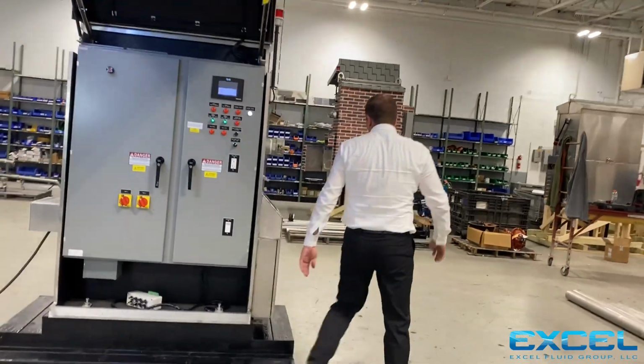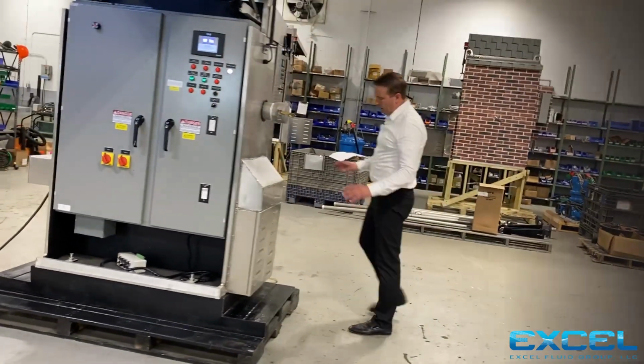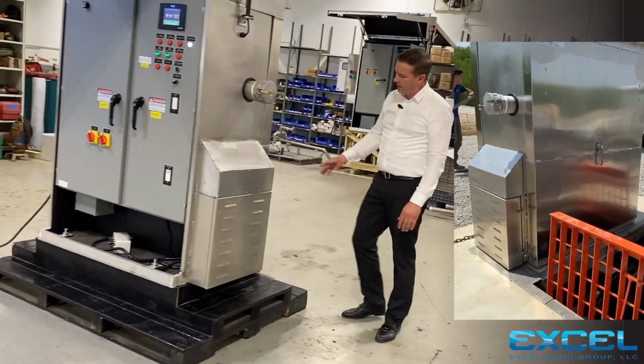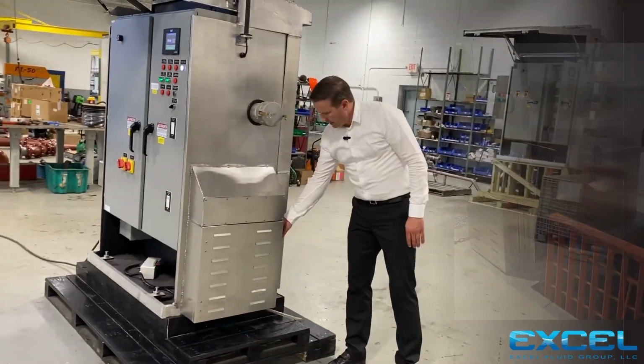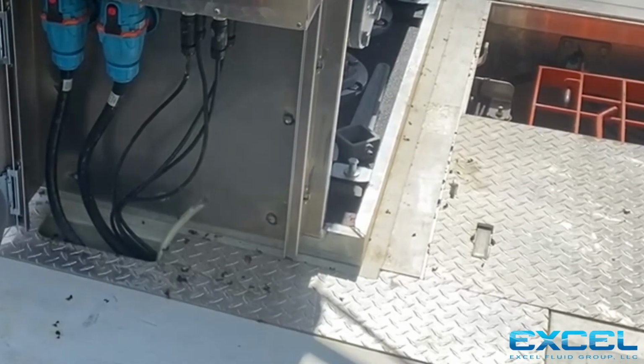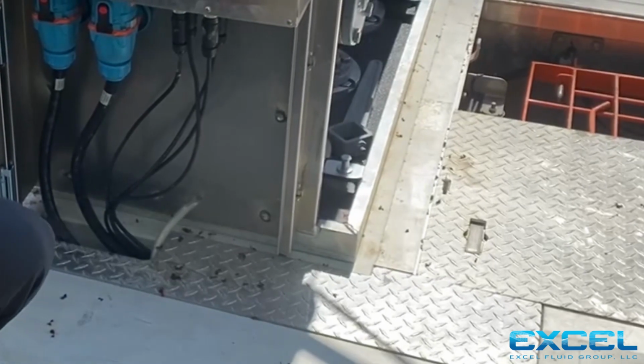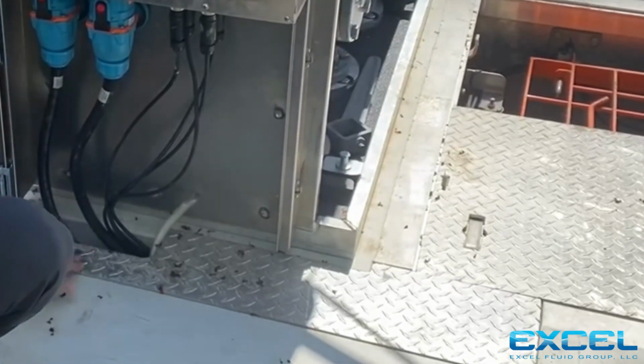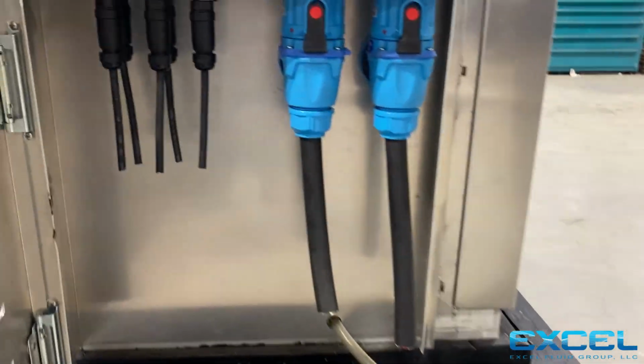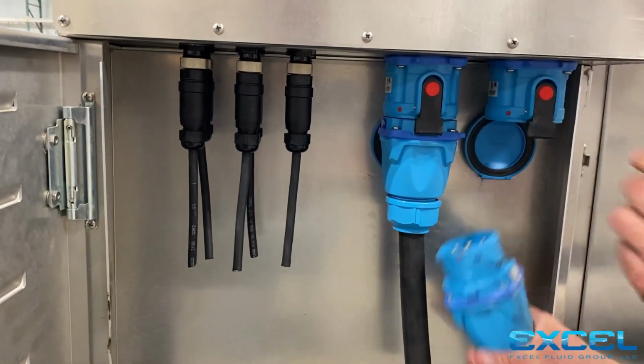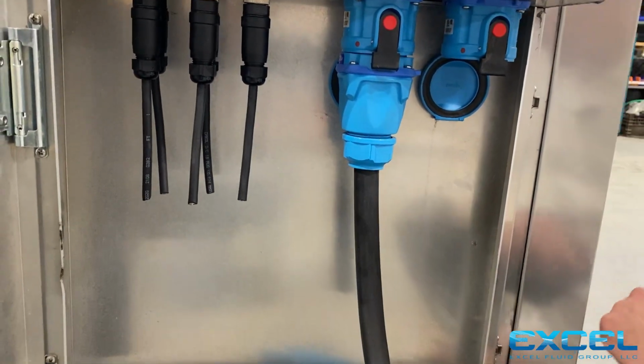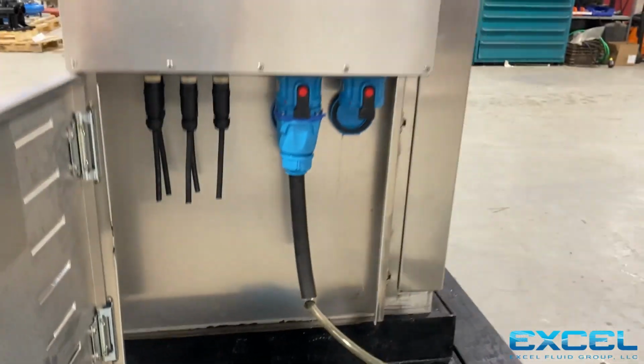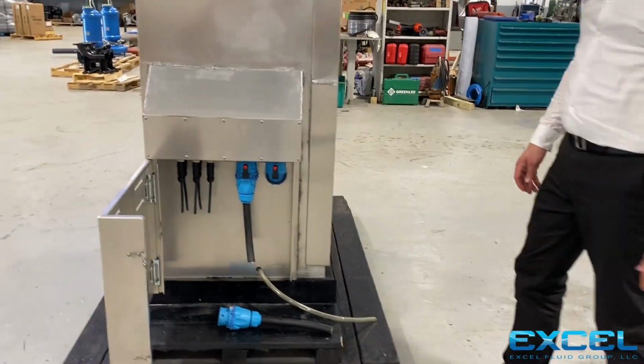Let's go around and look at our pump connection. So again, we're on top of the pump station right now. We'd be on a cable tray, and this access point for the plug wiring goes down the cable tray and into the wet well. We have our float connections and Meltric plugs where we simply release the plug, pull the wiring out of the cable tray, and take the pump with us for service or maintenance.